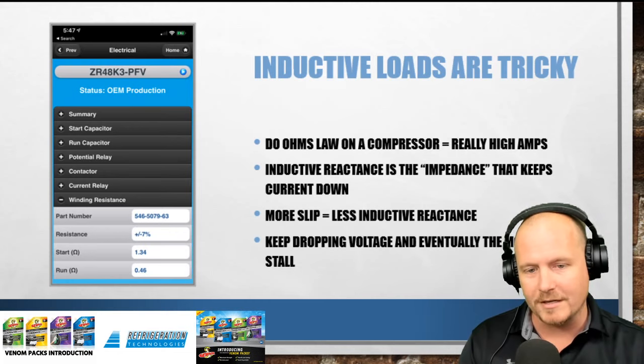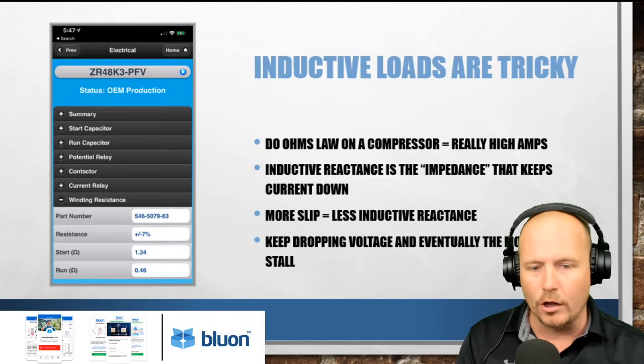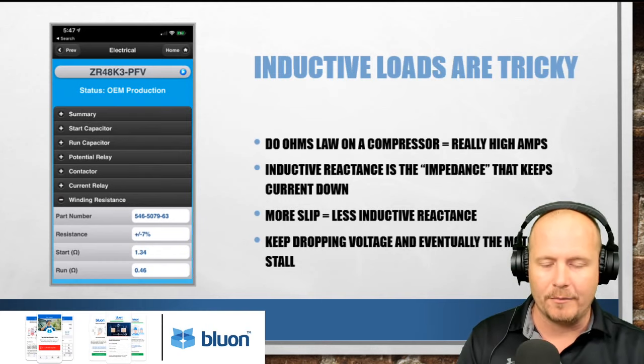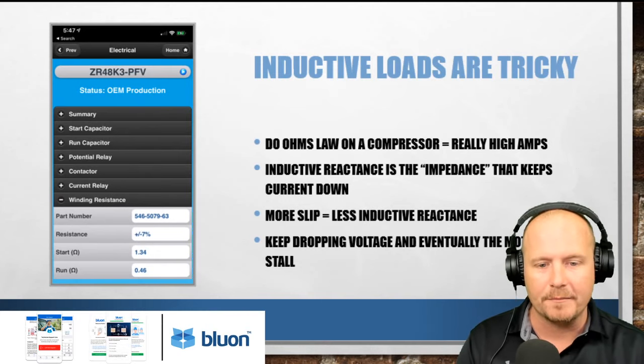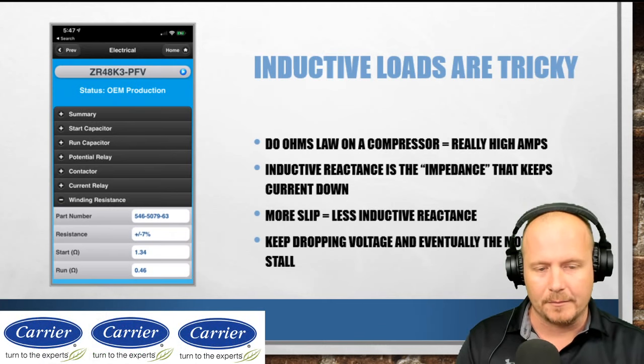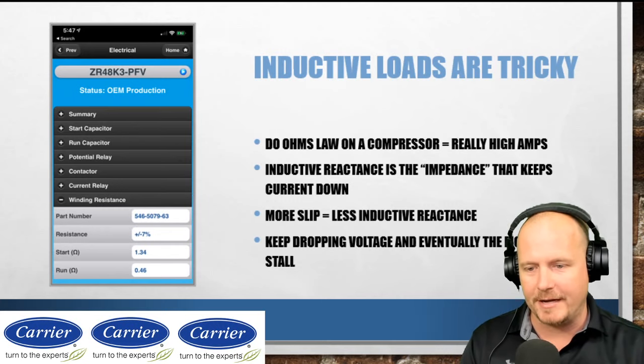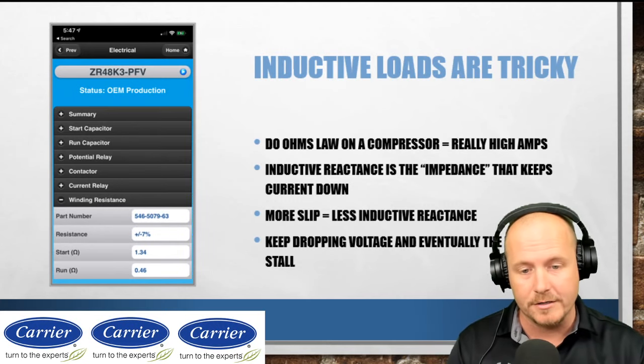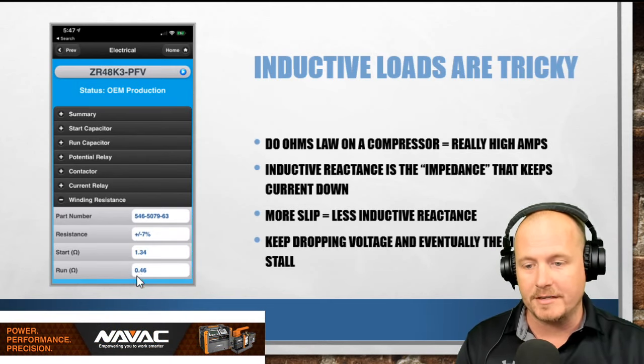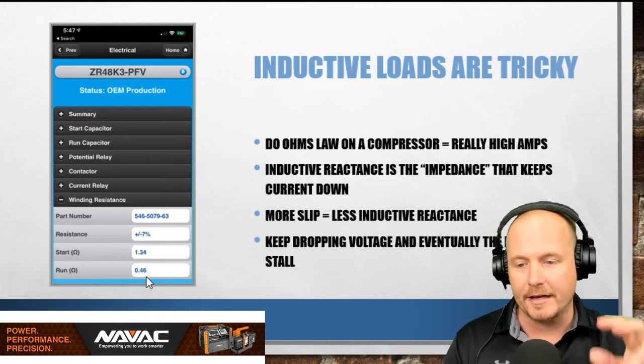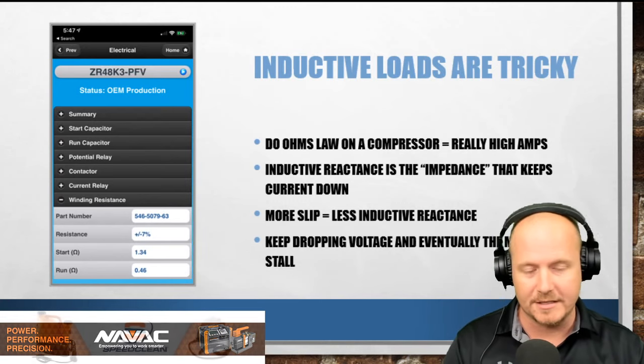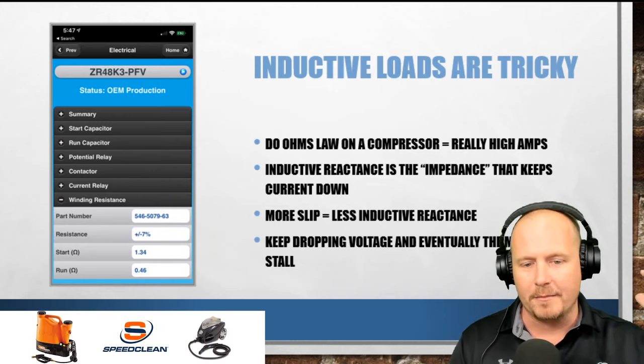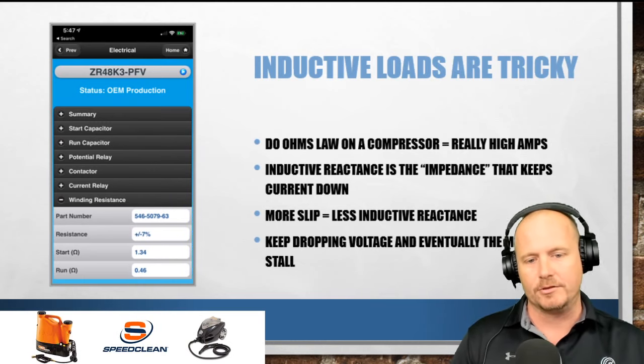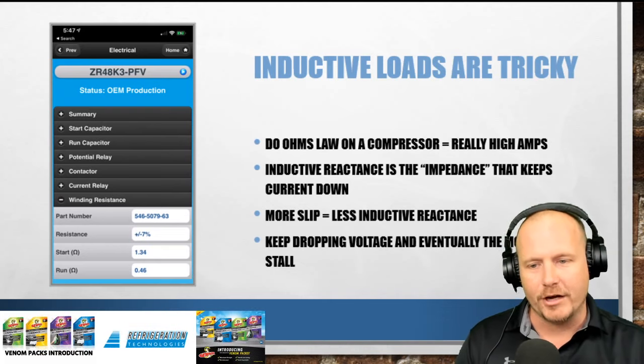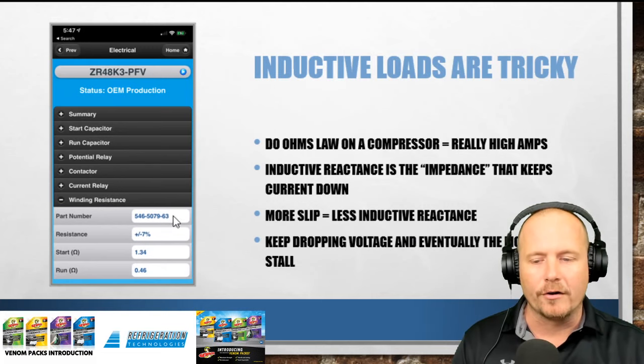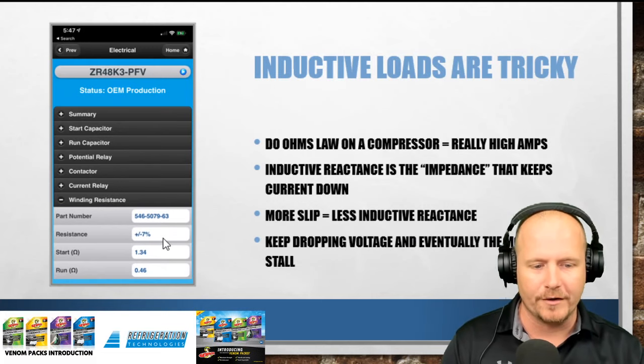If you take that 0.46 and you work Ohm's Law with that at a 240 volt power supply, I think it would be about 580 amps that compressor would draw if it was based on the resistance of that winding. In fact, a lot of meters, if you were to connect to this compressor, would say that it was shorted, a dead short across the windings at 0.46 ohms. And this is a huge mistake a lot of new technicians make. They measure across the windings and say, that resistance seems too low, the compressor's shorted. Well, no. Check it against the Copeland mobile app or whatever compressor manufacturer data you've got.